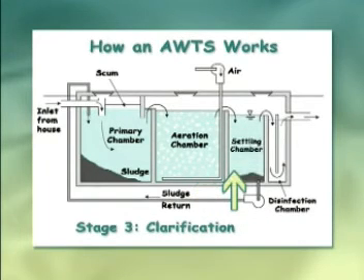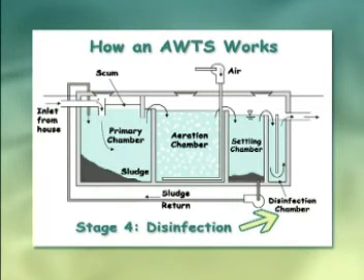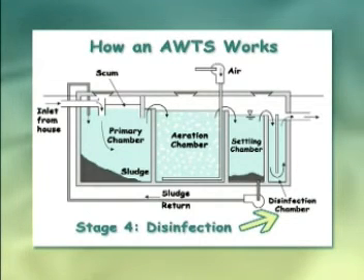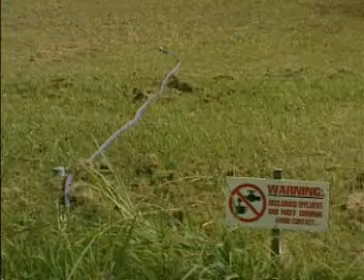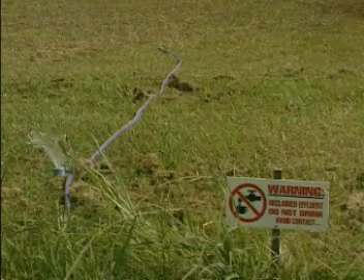Stage three is clarification, or settling of the remaining suspended solids contained in the wastewater. Stage four is the disinfection of the effluent. Effluent can be disinfected by using chlorine, ultraviolet light or ozone treatment before being discharged to a land application area. Stage five is pumping the effluent to the land application area, usually with surface or subsurface irrigation.